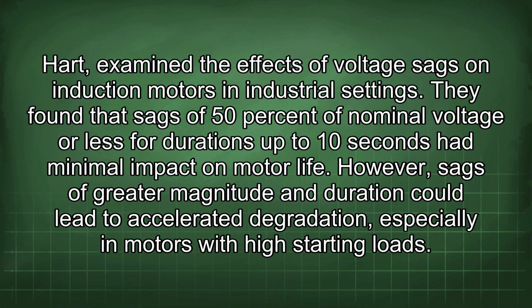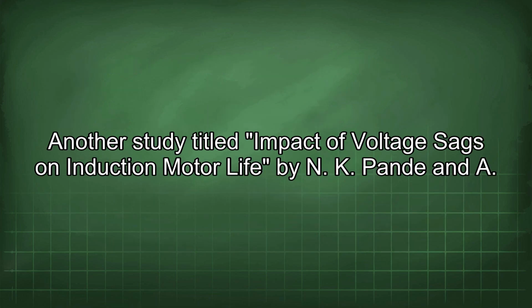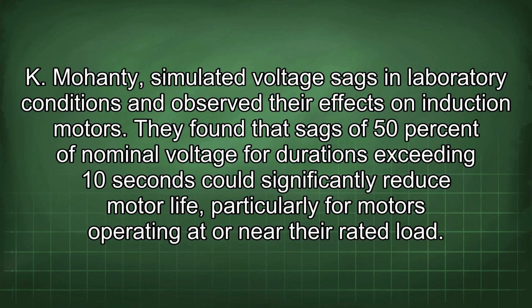Another study titled Impact of Voltage Sags on Induction Motor Life by N. K. Pande and A. K. Mohanty simulated voltage sags in laboratory conditions and observed their effects on induction motors. They found that sags of 50% of nominal voltage for durations exceeding 10 seconds could significantly reduce motor life, particularly for motors operating at or near their rated load.